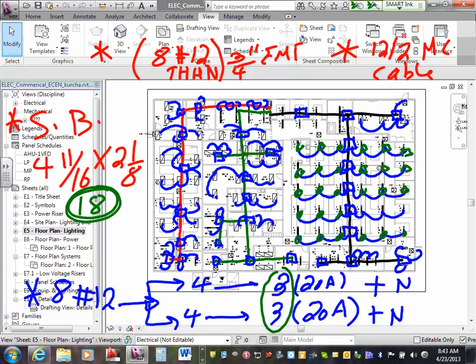If I use a neutral with a phase, then this 8 will give you, for every 3-phase circuit, you need 6. These 8 will give you only 4 circuits. If you want to go that route, then that assembly that we're using gives you only 4 circuits. You just have more, but you can remember, you can go up to 16 conductors. So you still can build with a neutral, I guarantee you. Even with pulling a neutral with every hot, guys, you still can build this system this way. Because remember, the 3/4 inch can go up to 16 conductors you can fill in it. I'm only filling it up to what? 8. So if you add even a neutral with each circuit, so these 3 circuits, that will give you 3 wires, 6 wires, plus a neutral with each circuit.